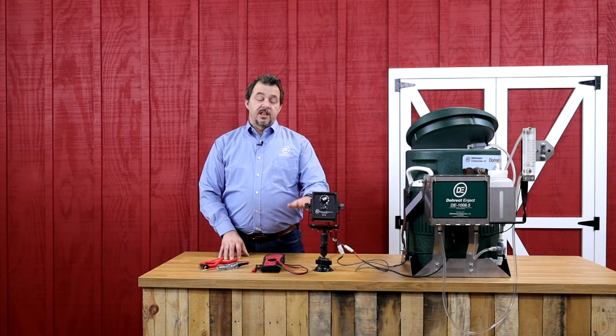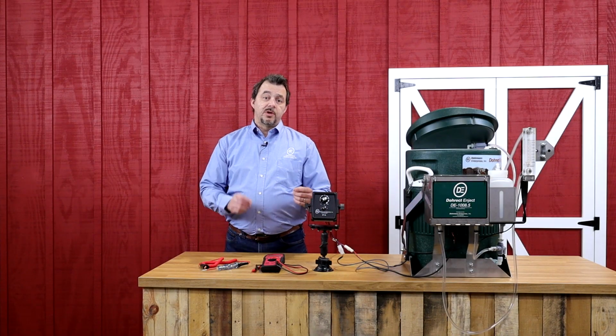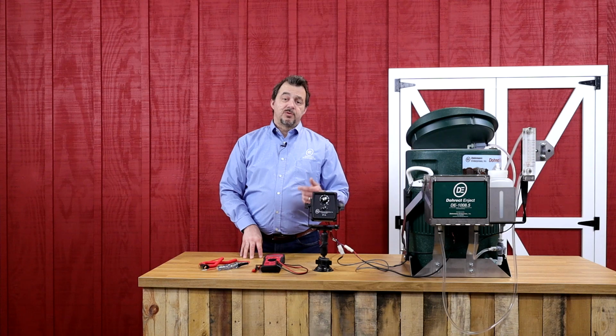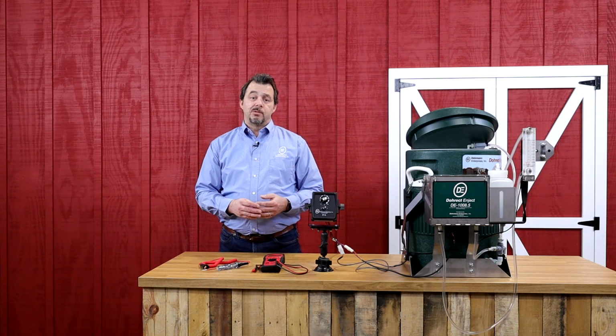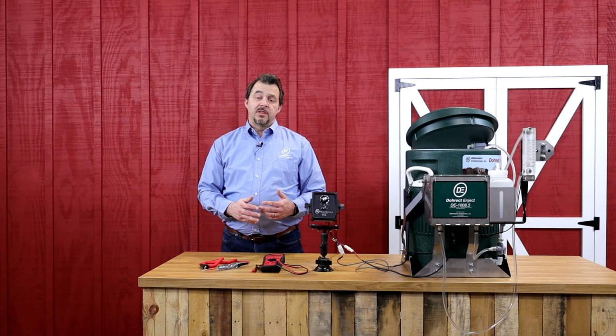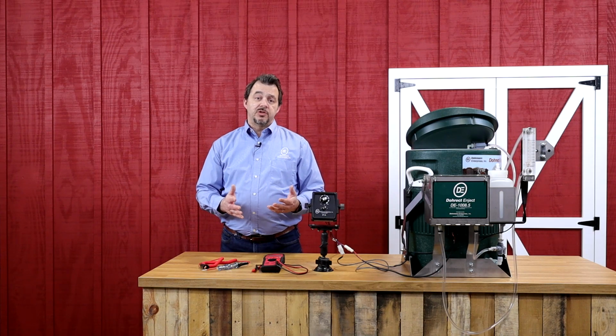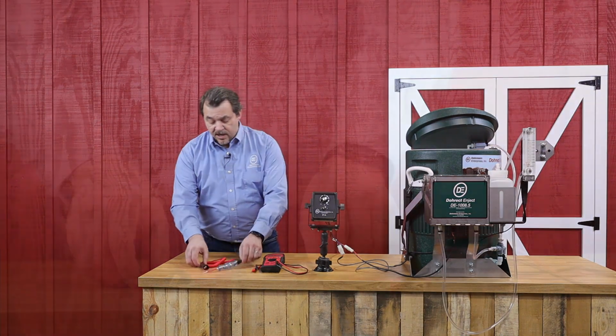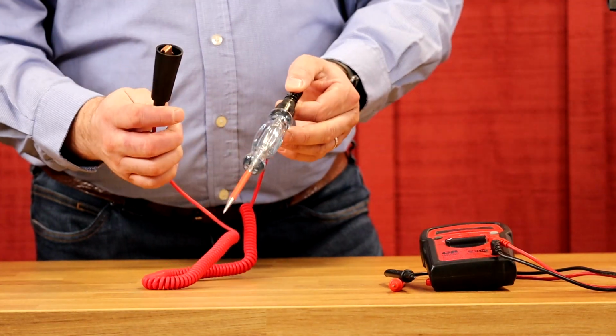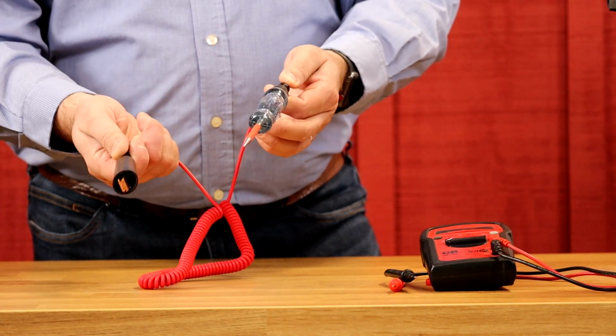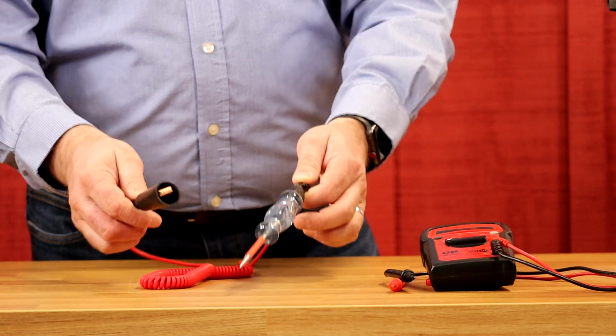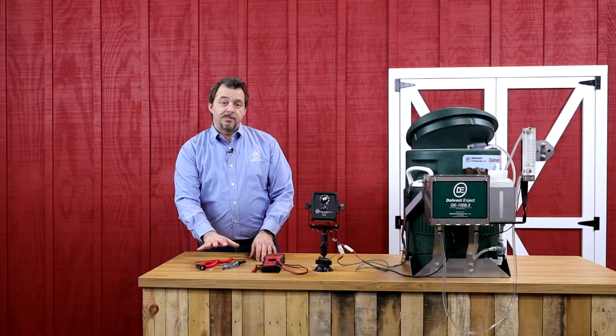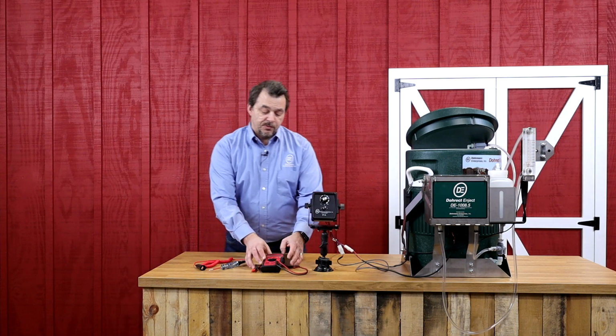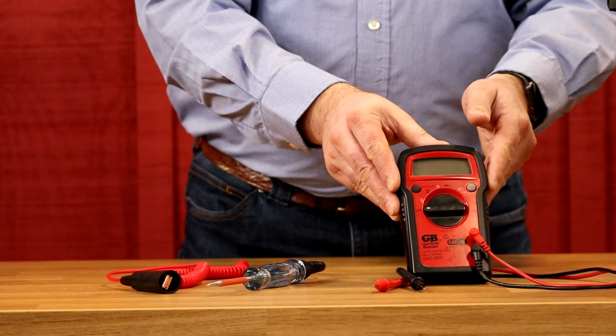So if we find out that the LED on the control is not turning on, or when you bypass the controller, the pump is running backwards, we have to start looking at troubleshooting the wiring and in turn the power supply. So generally speaking, when we look at tools to troubleshoot wiring, we've got two different options that are most commonly found. One option is what's referred to as a trouble light. The trouble light isn't the best option that we have. We would much prefer you to use a tool like this, a multimeter.